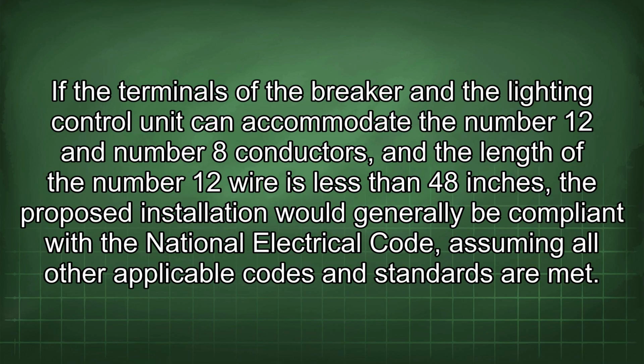If the terminals of the breaker and the lighting control unit can accommodate the number 12 and number 8 conductors, and the length of the number 12 wire is less than 48 inches, the proposed installation would generally be compliant with the National Electrical Code, assuming all other applicable codes and standards are met.